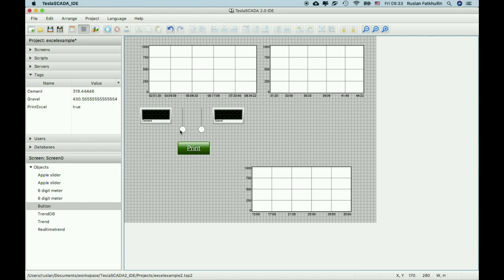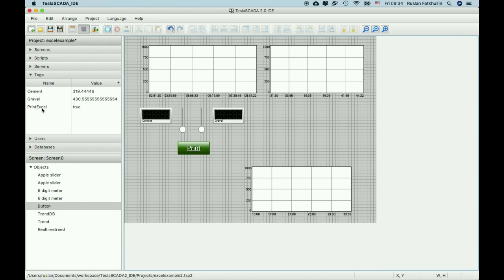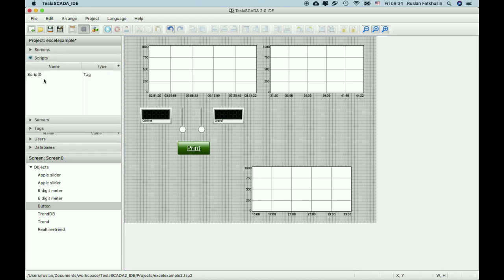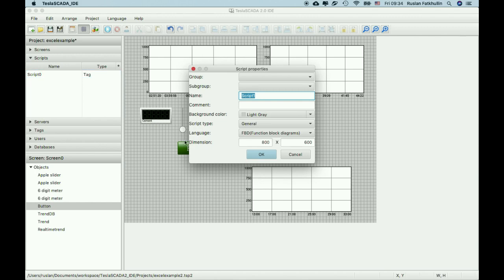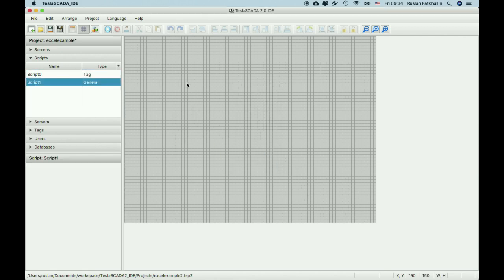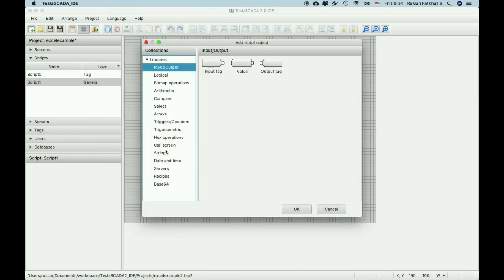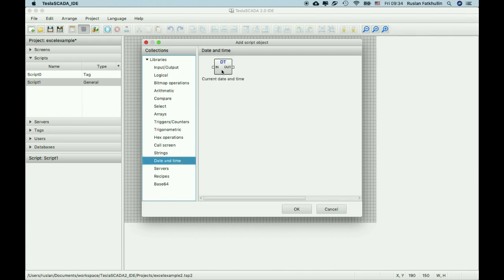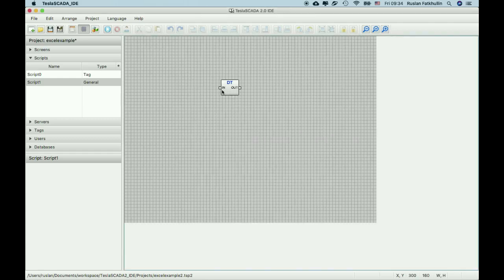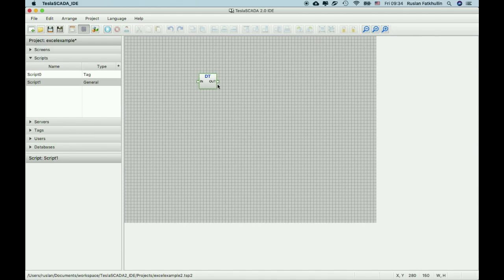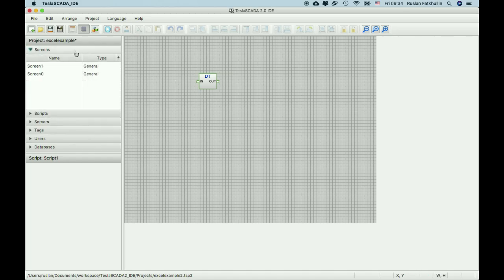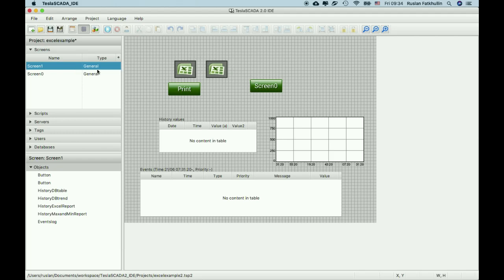Of course you can save your Excel reports and screenshot not only by clicking print, but also you can bind this tag to the schedule. For example, if you want to report print every day at 6am or 7am, you can use for this purpose FBD scripts and date and times. By choosing this object you can get current hour or current minutes and compare this value with the time you want your tag is on. And at this moment print the Excel reports.